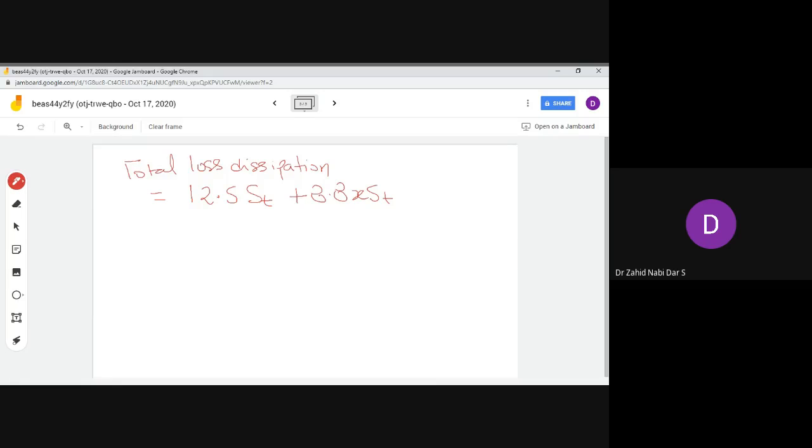But yesterday you saw that I applied a formula there directly. So now if you see certain commonalities between the area and the factors: the total surface area of the walls of the tank and tubes. The tank area, you know, is st, and the tube area is x times st. So st is common, so it will become st times (1 plus x).